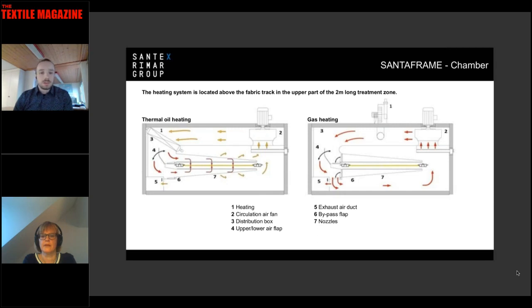When the pin chain stops, the hot airflow into the nozzles is immediately diverted by pneumatically operated bypass flaps that close completely. The hot air is routed into a bypass where the process temperature is maintained. Once production restarts, there is no need to reheat the circulating air and fabric treatment resumes under optimum conditions at the required production speed.